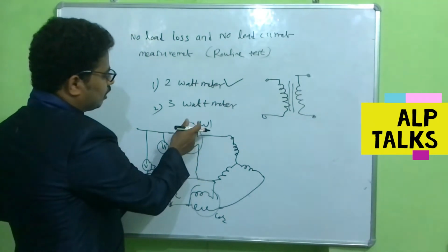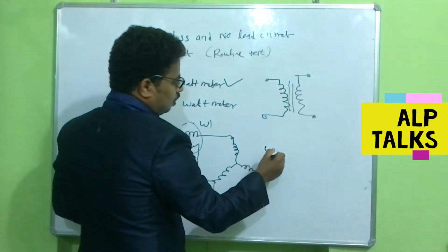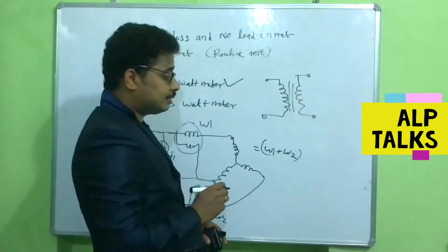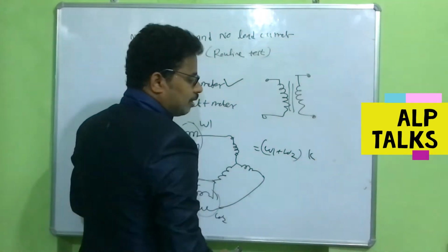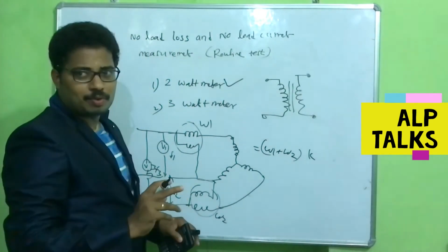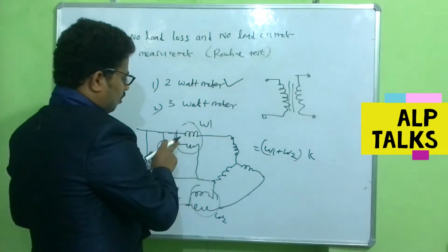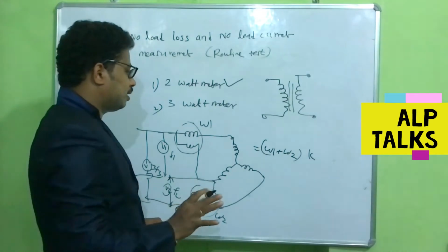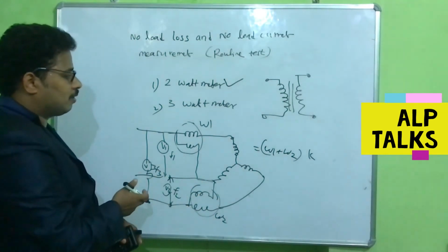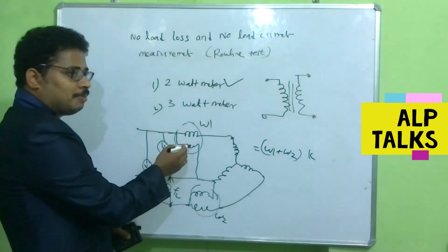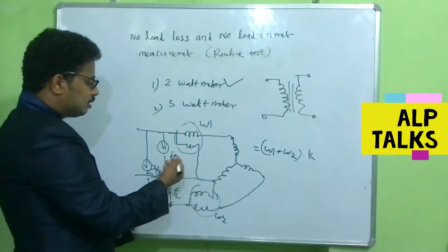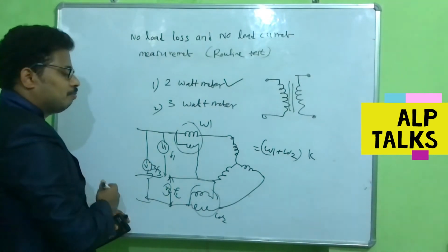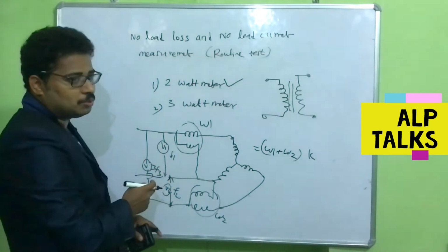In this method, whatever the readings we got in W1 and W2, we can simply add those two values, and if we have any wattmeter multipliers, then we can use those multipliers. If the coil connections are wrong, the readings may be negative, so you can take care of that. So this is one of the arrangement points. Here wattmeters are closer to our transformer terminals, and the voltmeter and frequency meters are connected just before the wattmeters. This is the correct way to measure it.